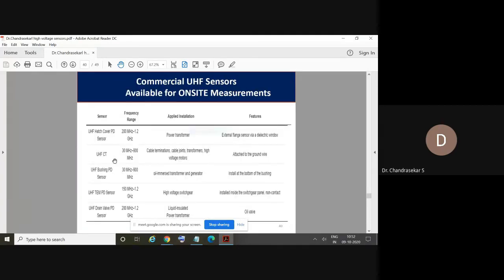And these are some of the commercial UHF sensors available at different frequency ranges, and for what application they are used. Whether it's for transformers or cable terminations or joints or for generators or any high voltage switchgears, for each and every high voltage equipment, a separate UHF sensor technology is available. So we can select based on our requirement.